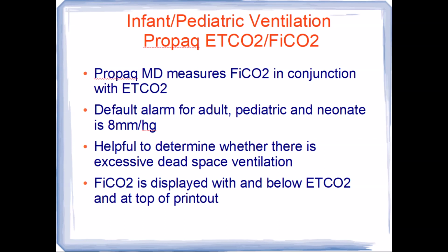The other way that we can tell, once you have that end tidal CO2 attached and you look at the right side of the ProPaq, where the end tidal CO2 is, you'll see a small number just below that. It says FiCO2. That is the fraction of inspired CO2. So on our ProPaqs, the default alarm for all the patients, for adult, pediatric, and neonate, it will alarm if it is 8 millimeters of mercury or greater. So keep that in mind. You can look, the goal is to have that FiCO2 0 or as close to 0 as possible.